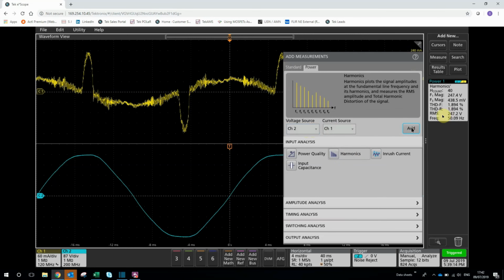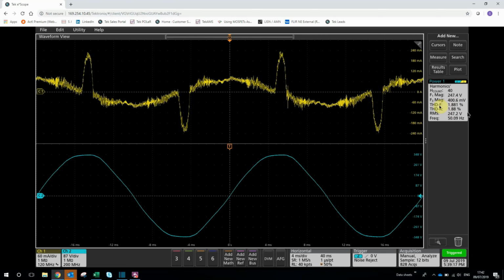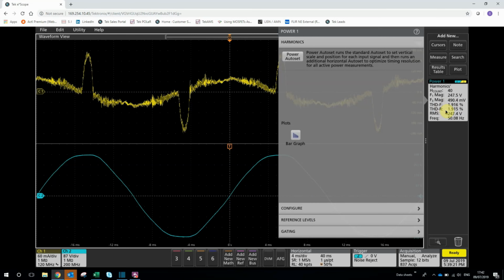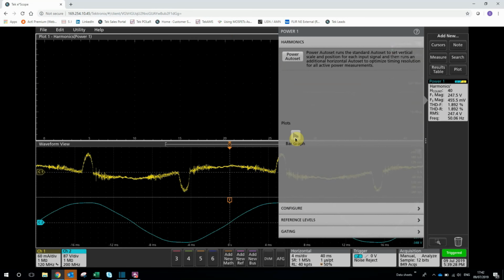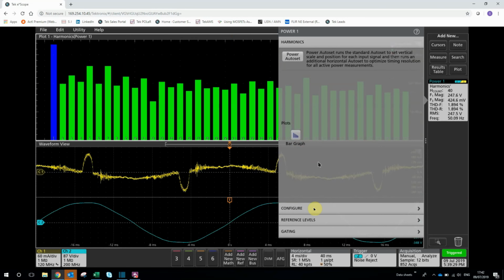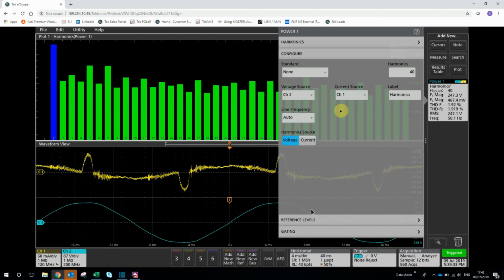Cool. So already we're getting some measurements here, but we can configure that a little bit further. So double tapping on the measurement badge here on the right hand side, we will first add a bar graph of the harmonics to give us a visual display, which is quite nice. Come down here and press configure. Here's where we can set things like our line frequency, so 50, 60 Hertz, 400 Hertz, or a custom value.